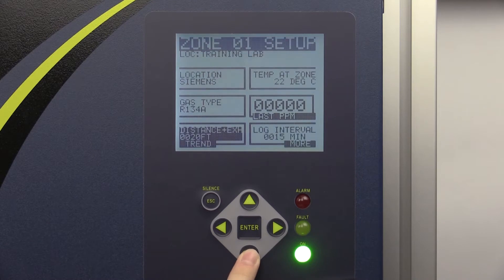Use the Distance tab to specify the distance of the zone from the monitor. This distance is equal to the length of the tube you measured during installation. For ports without manifolds in active solenoid connection blocks, set this distance to zero. This will cause the system to bypass these zones when cycling through the zones to take readings.